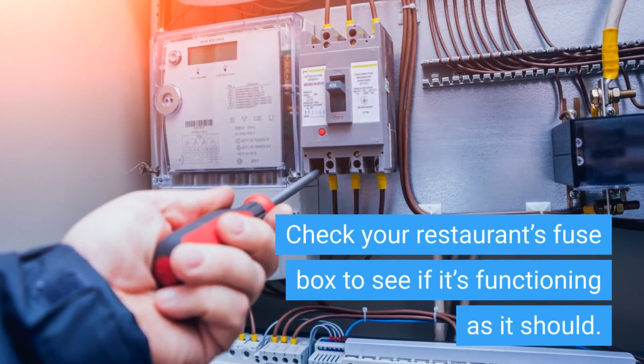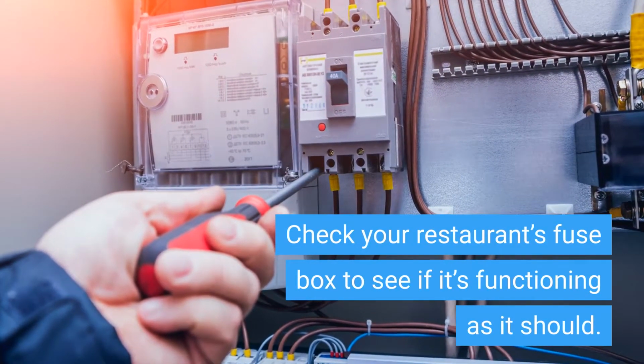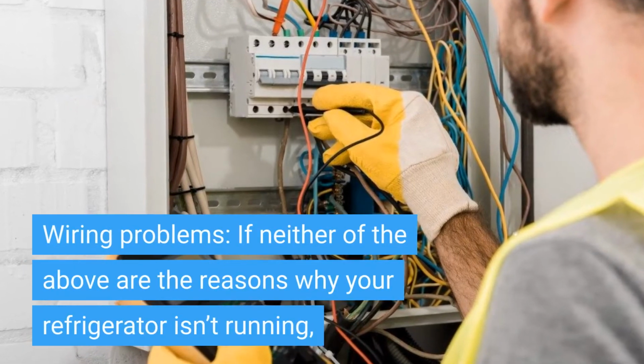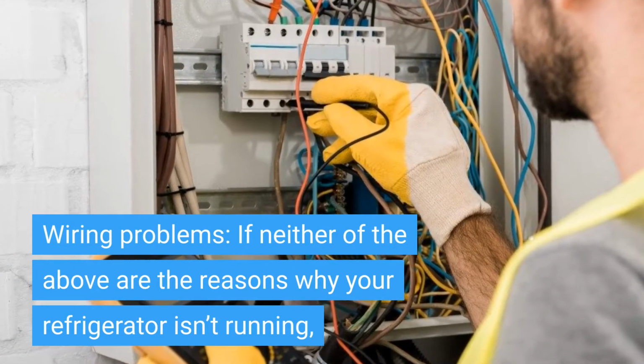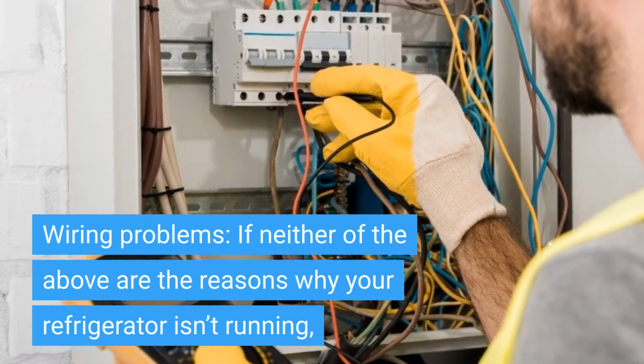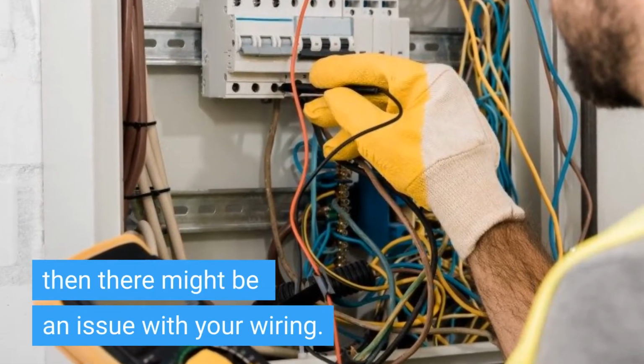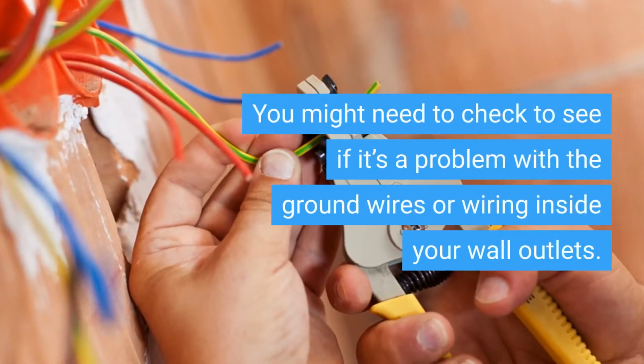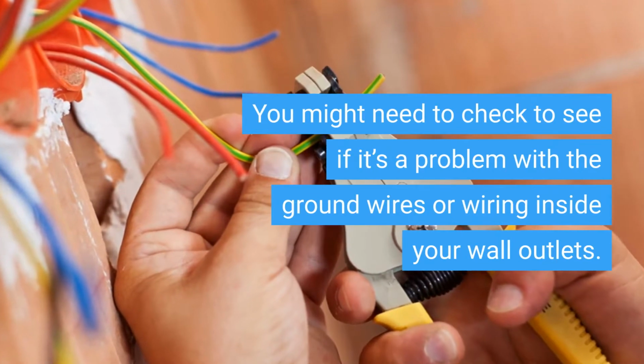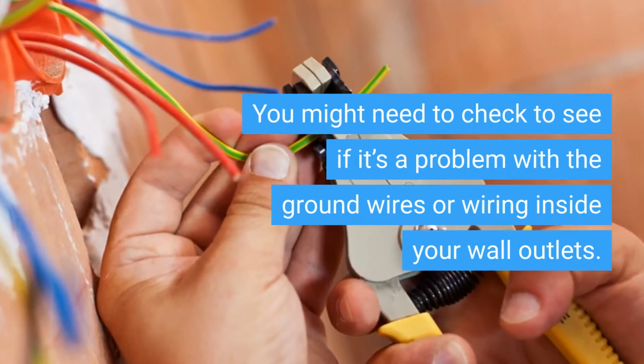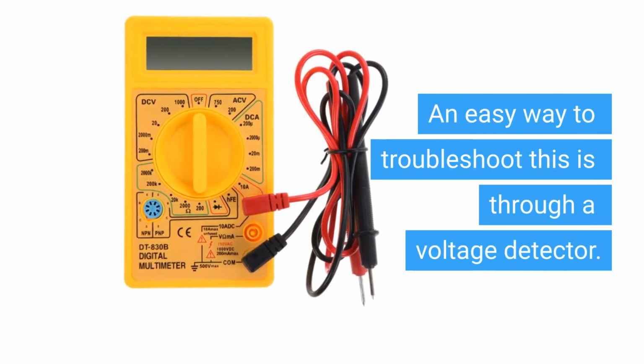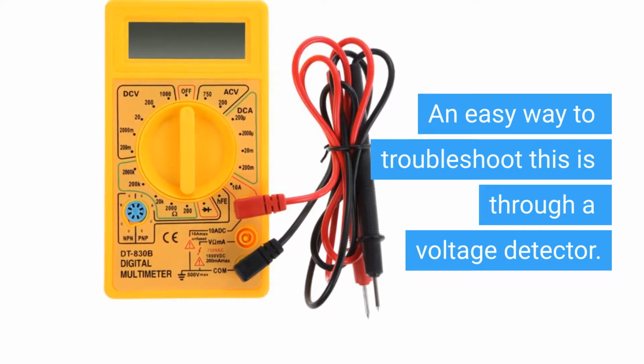Blown fuse. Sometimes a commercial refrigerator fails to power up because there's a tripped circuit or blown fuse box. Check your restaurant's fuse box to see if it's functioning as it should. Wiring problems. If neither of the above are the reasons why your refrigerator isn't running, then there might be an issue with your wiring. You might need to check to see if it's a problem with the ground wires or wiring inside your wall outlets. An easy way to troubleshoot this is through a voltage detector.